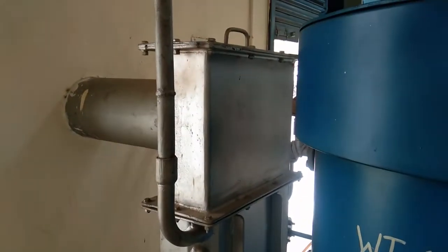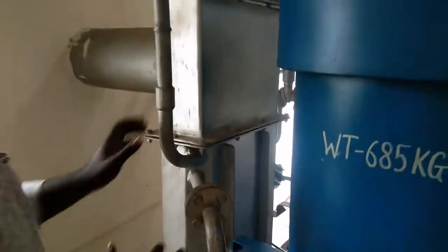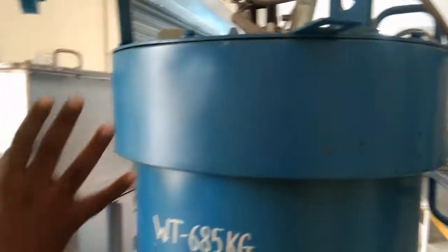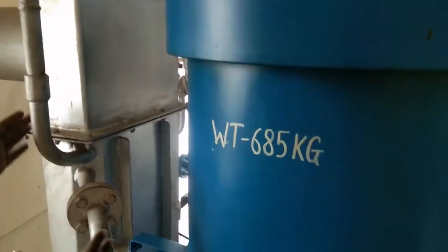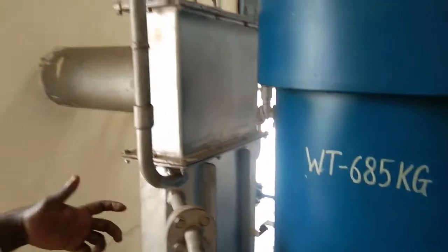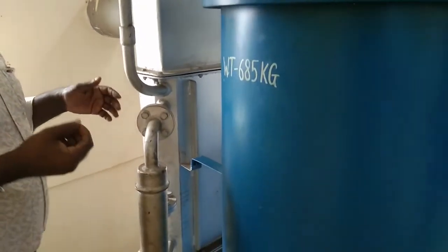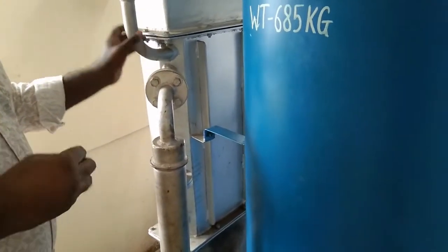There is a silver color setup available, which is known as the economizer. Why do we utilize this economizer? This economizer coil is used to preheat the water going into the drum. Before supplying the water into the drum, we preheat the available water. From this we can easily reach the saturation temperature, or saturation level of steam, for the developed working fluid. Likewise, we can enrich the heat through this setup. So the economizer coil is used to preheat the supply water.